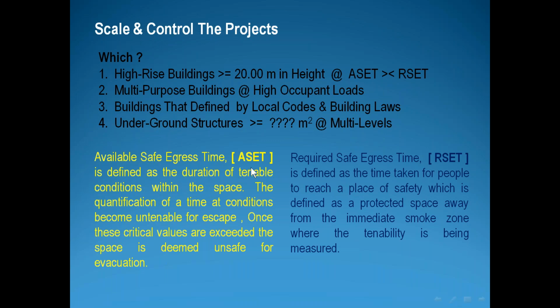Again, this is the definition of the available safe egress time: it is defined as the duration of tenable conditions within the space. The quantification of the time at which conditions become untenable for escape. Once these critical values are exceeded, the space is deemed unsafe for evacuation. This is why the available safe egress time shall be calculated according to the architect layout. And if we have any modifications in the main structure of this design, we have to recalculate the available safe egress time or escape time.